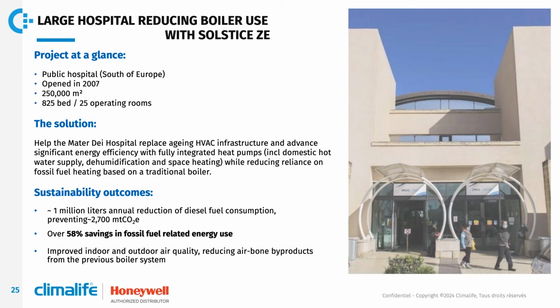So the existing HVAC infrastructure was old, and the reflection was to renew this HVAC installation with a new one. And the solution selected here was to use R1234ze in integrated heat pumps. That means that we are able here to produce a domestic hot water supply, dehumidification, and the heating of all this space.